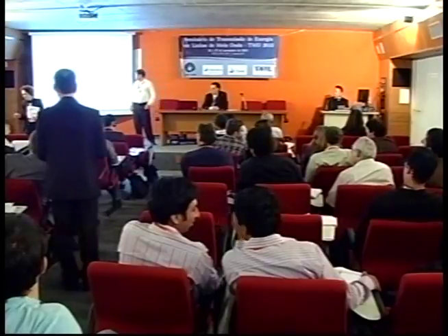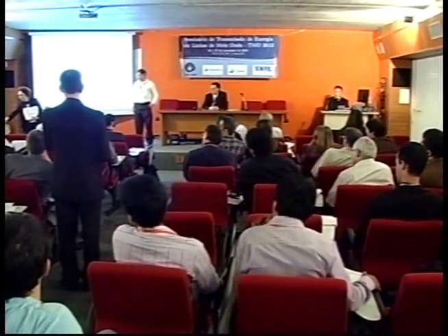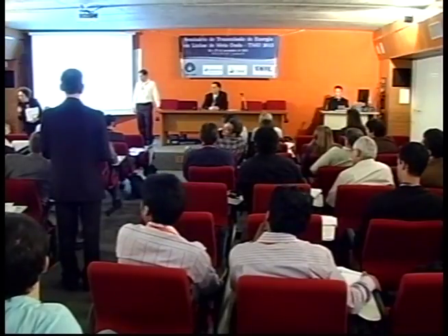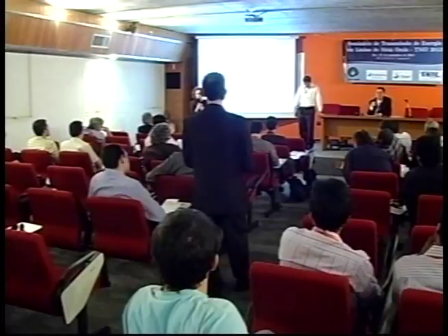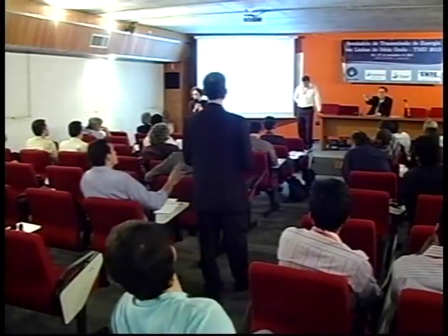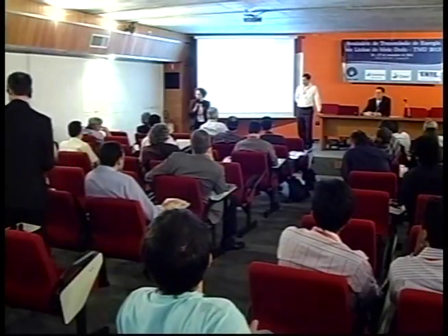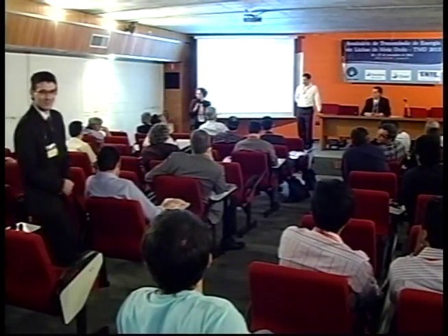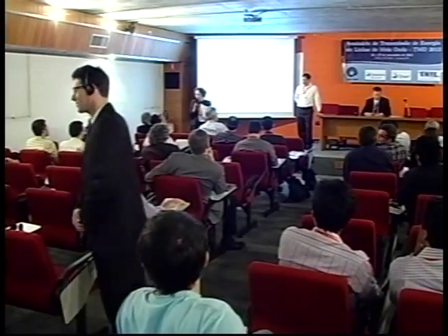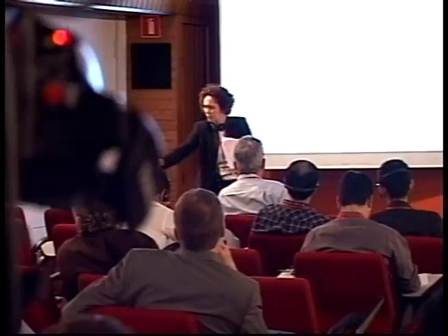Just to summarize it: the model of the line created this difference. Yes, the model of the line, because we do not work with the Marti model. The Marti model for dependence of frequency in the parameters does not work very well. We do not consider it to be suitable. So to represent the frequency, we use the phase model in PSCAD. It gives us a good response. So the difference is only the model of the line.